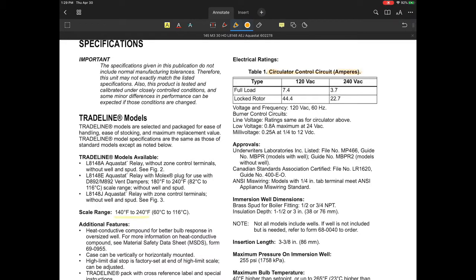One of the other things that would be relatively important to look at is the electrical ampacities of the circulator circuit. A lot of these Aquastat relays have the ability to control the circulator, or at least provide power, switching from the main power through the Aquastat relay to allow you to energize a circulator in conjunction with the boiler. And we'll look at that circuit and identify how that works. The full load ampacity on a 120 volt system is going to be 7.4 amps, and the locked rotor circuit they're calling is 44.4 amps. So if you have a 240 circuit, as you can tell, they're cutting that roughly in half.